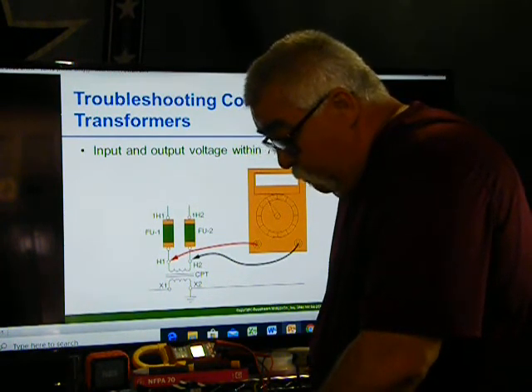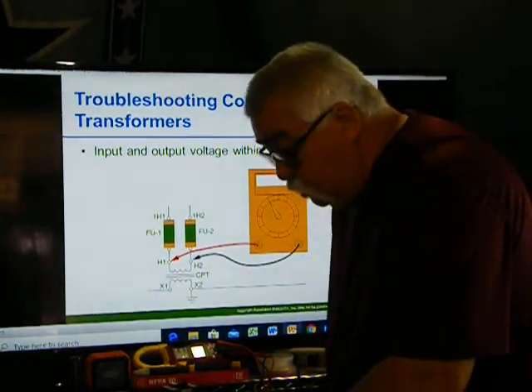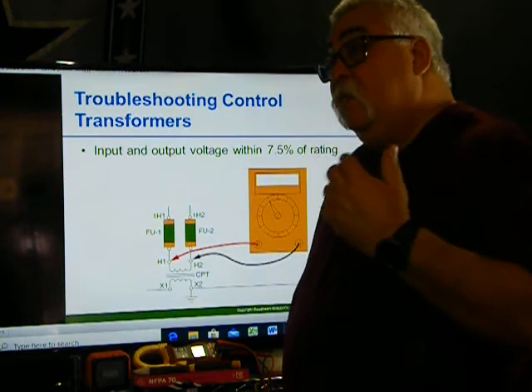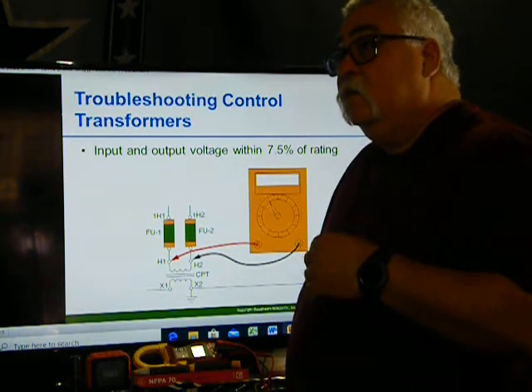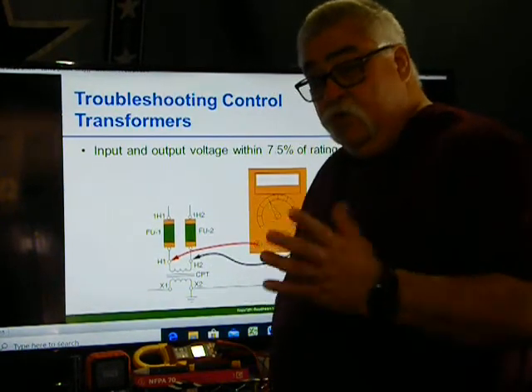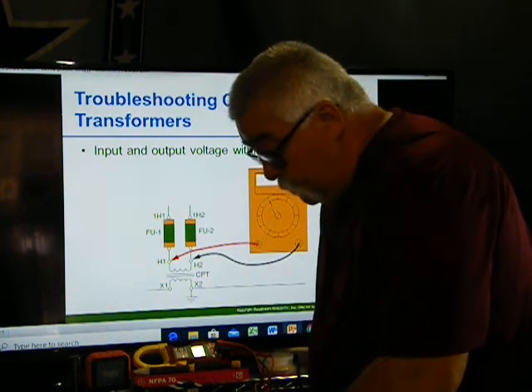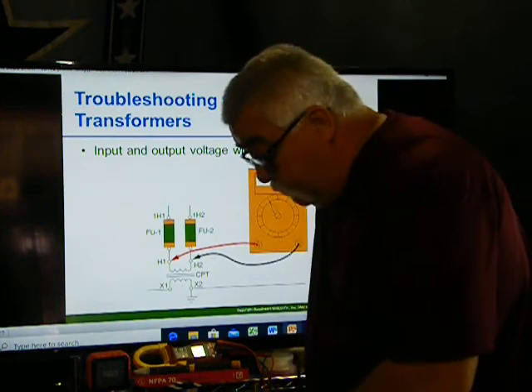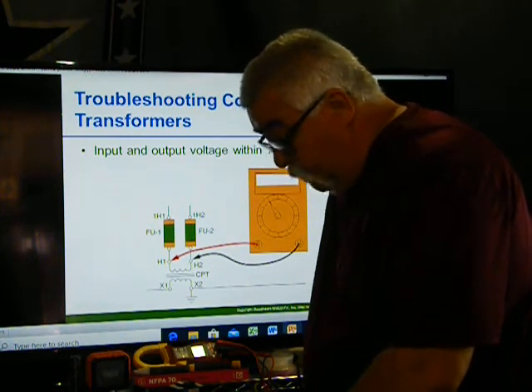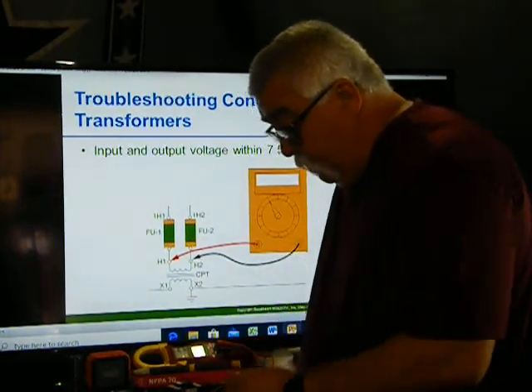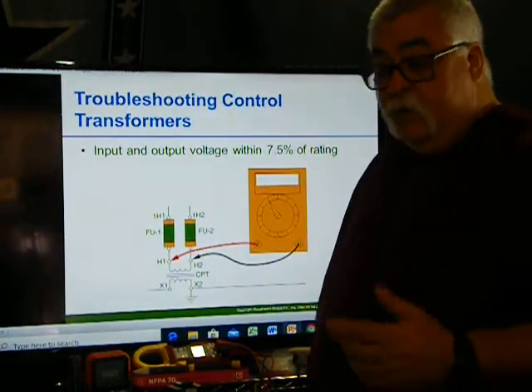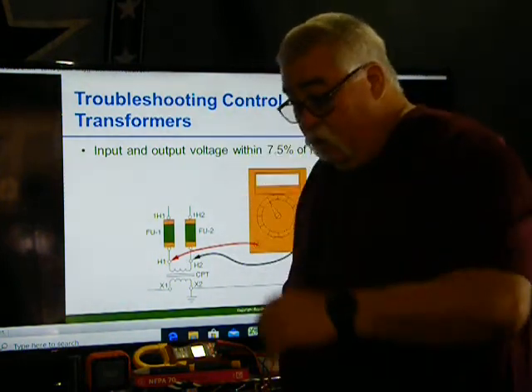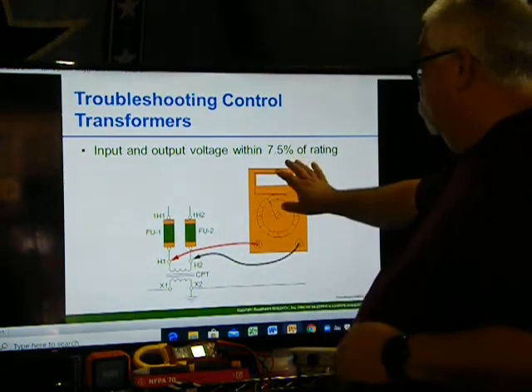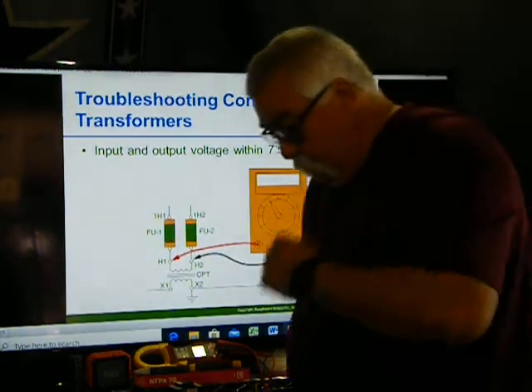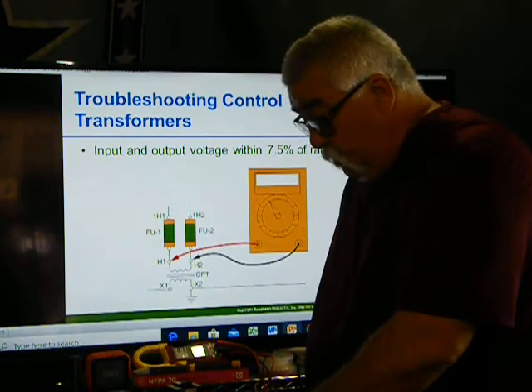So 480 times 7.5% equals 36 volts. So I can lose 36 volts. So 480 coming in minus 36 would be 444. And as long as you're in that range, you're okay. Output voltage: 120 times 7.5% is 9 volts, so I can go from 111 up to, I forgot to do it upwards, so it's 36 volts up or down, within 7.5% of the rating, up or down. So it says 444 and 516. And then for the 120 volts, it's 111 to 129, because it's 9 volts up, 9 volts down.